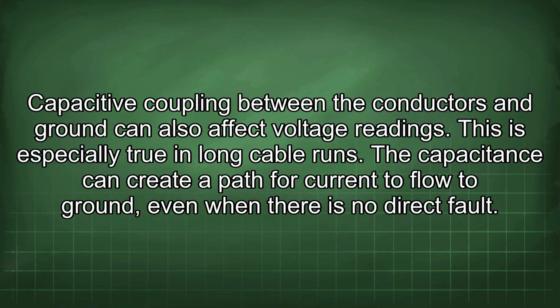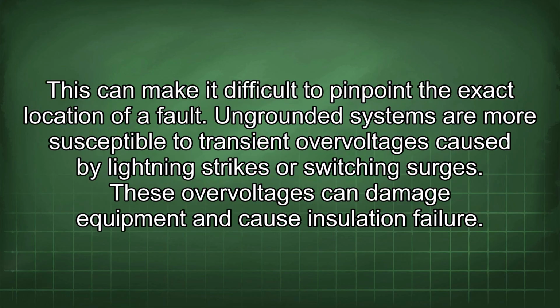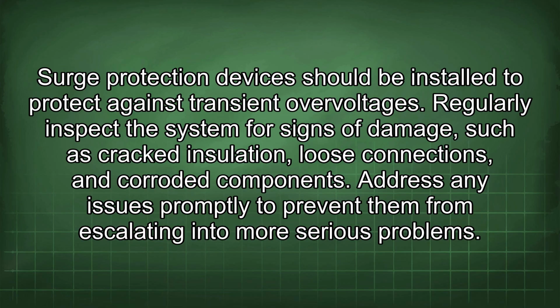Capacitive coupling between the conductors and ground can also affect voltage readings. This is especially true in long cable runs. The capacitance can create a path for current to flow to ground, even when there is no direct fault. This can make it difficult to pinpoint the exact location of a fault. Ungrounded systems are more susceptible to transient overvoltages caused by lightning strikes or switching surges. These overvoltages can damage equipment and cause insulation failure. Surge protection devices should be installed to protect against transient overvoltages.